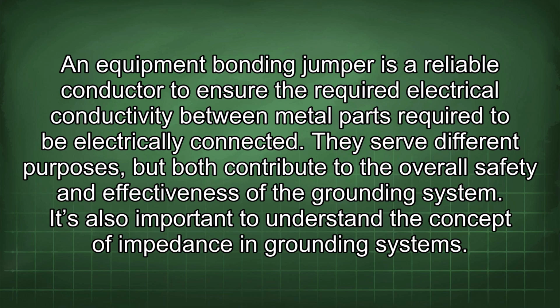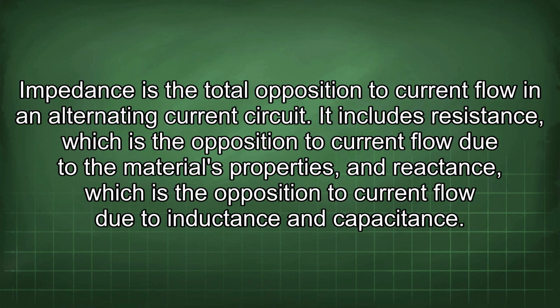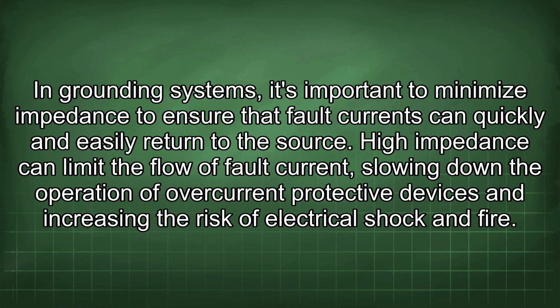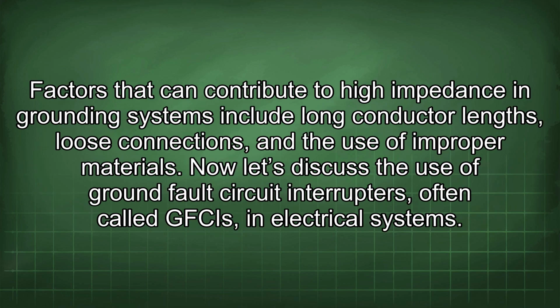It's also important to understand the concept of impedance in grounding systems. Impedance is the total opposition to current flow in an alternating current circuit. It includes resistance, which is the opposition to current flow due to the material's properties, and reactance, which is the opposition to current flow due to inductance and capacitance. In grounding systems, it's important to minimize impedance to ensure that fault currents can quickly and easily return to the source. High impedance can limit the flow of fault current, slowing down the operation of overcurrent protective devices and increasing the risk of electrical shock and fire.